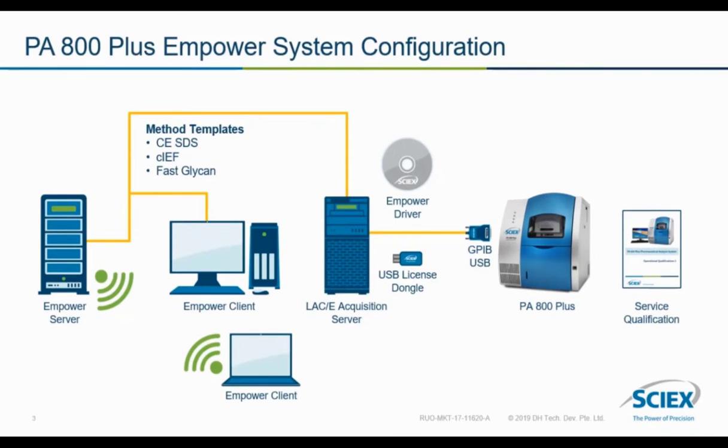The Empower driver will be installed in the LACE computer, along with the Sciex USB license dongle. It allows data acquisition from the PA800 Plus. This driver can also be installed on the client computers for data analysis purposes without the need of the USB license key dongle.